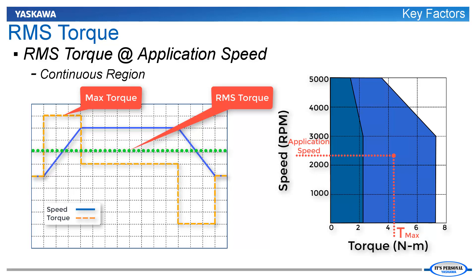So, it is also important to ensure that the RMS torque at application speed falls within the continuous region of the speed torque curve.